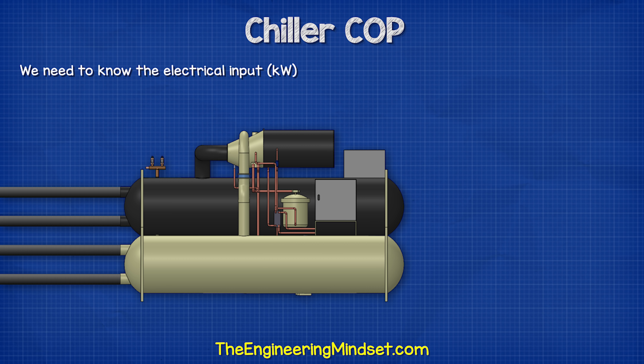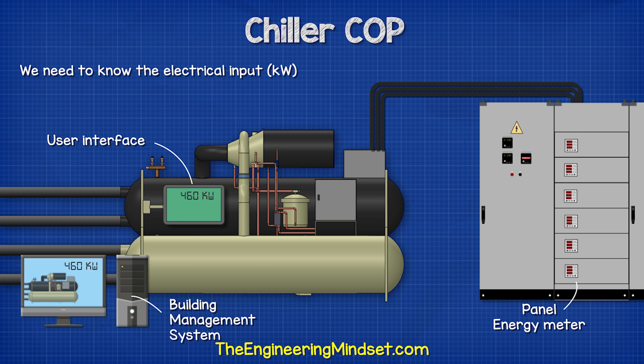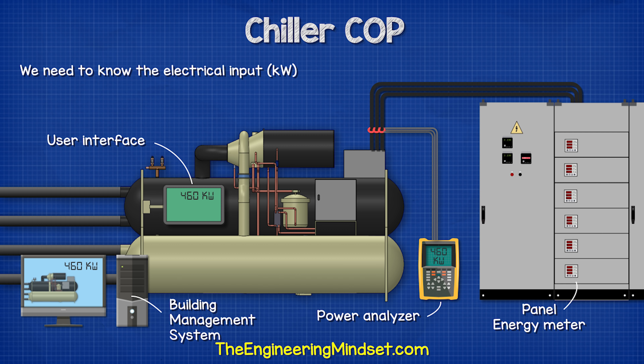The first part we need is the electricity in, and that's measured in kilowatts. This number is very easy to get hold of. You can find this information on a digital energy meter, which you will likely find on the electrical panel. Alternatively, it should be displayed on the user interface of the chiller or even on the building management system. Otherwise, you will need to connect a temporary energy meter. The electricity demand will vary depending on the cooling load — this is not a fixed value.